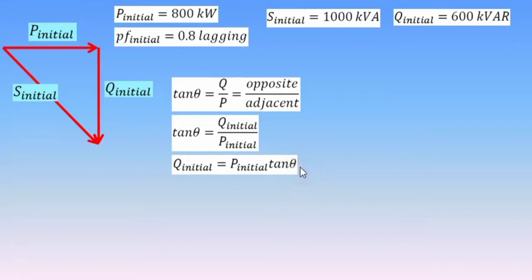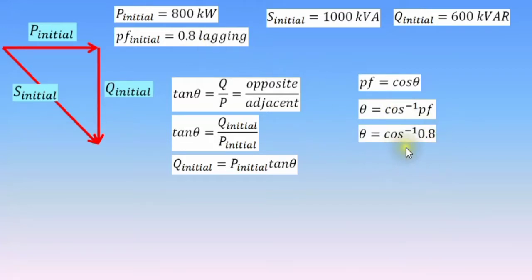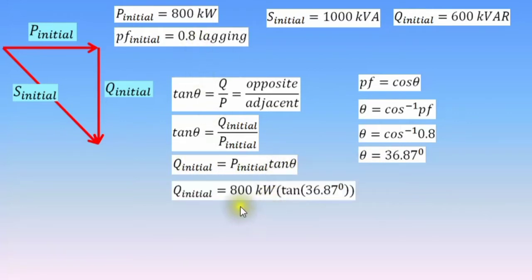Let's determine the value of its power factor angle. To determine that, from the formula power factor equals cosine theta, theta is equal to the inverse cosine of the power factor. Substitute 0.8 to this formula, the inverse cosine of 0.8, the angle is 36.87 degrees. And substitute this value to this equation. The value of its initial effective power is 800 kilowatts, so we have 800 kilowatts times tangent 36.87 degrees, the value is 600 kVAR. It is the same value we have using Pythagorean theorem. So we can use these two methods to determine its reactive power.